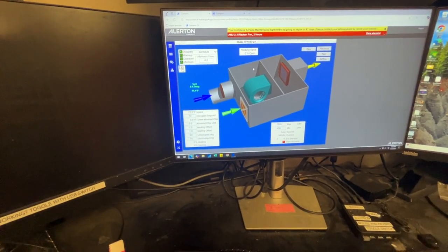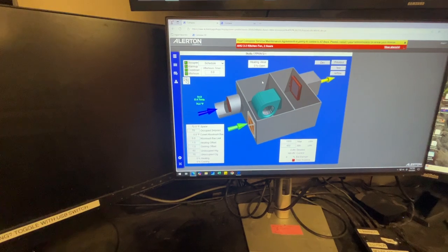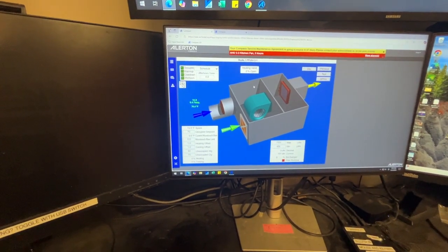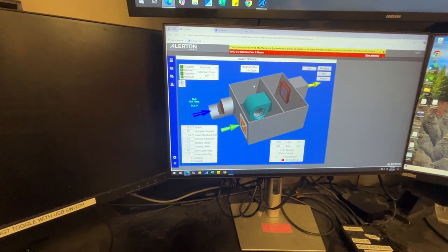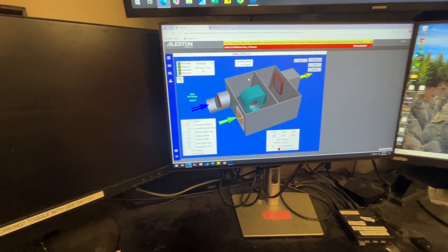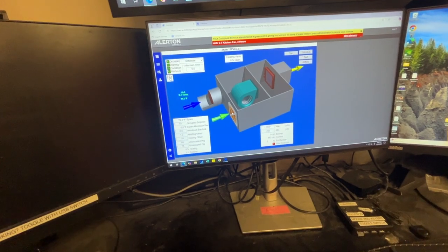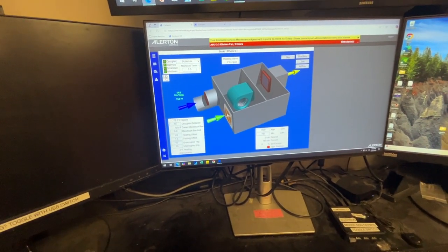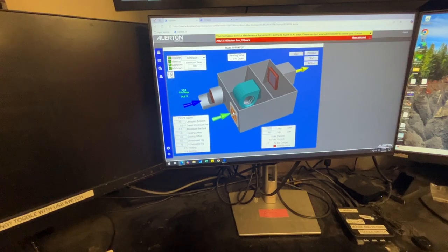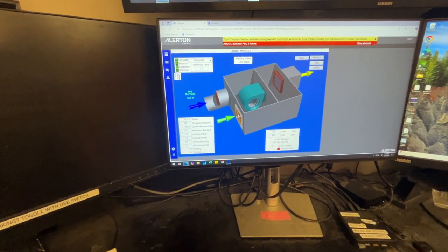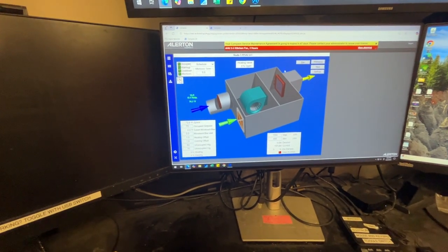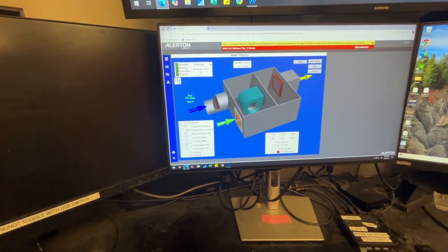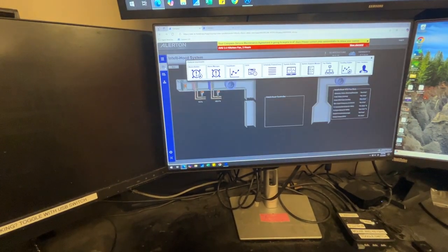These are a real pain in the butt to work on. The access panels are in the pre-function in front of the entry. You've got to take a lift up and climb off the lift onto a catwalk to get to them. They have filters in them. The filters, we put like a MERV 3 on them because they only get used for the heating coil. So they do not need to be changed all the time. They run maybe 1 month a year, a little more. It's very rare. And there is baseboard heat in there as well. So that is air handler 1A-3.